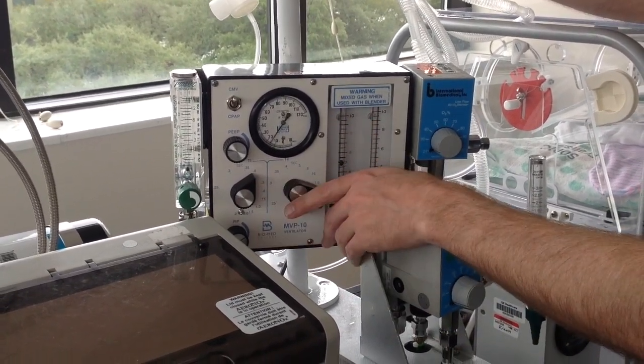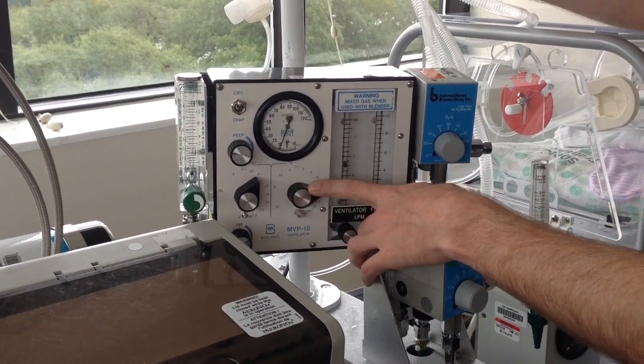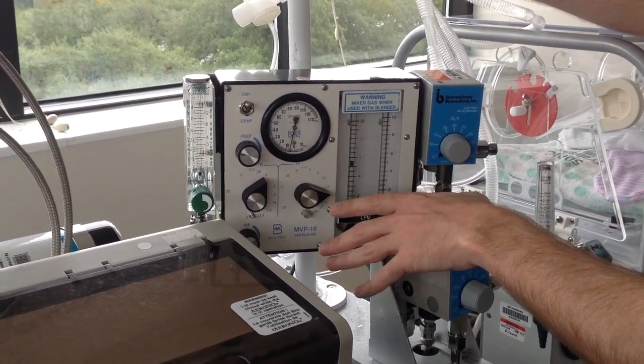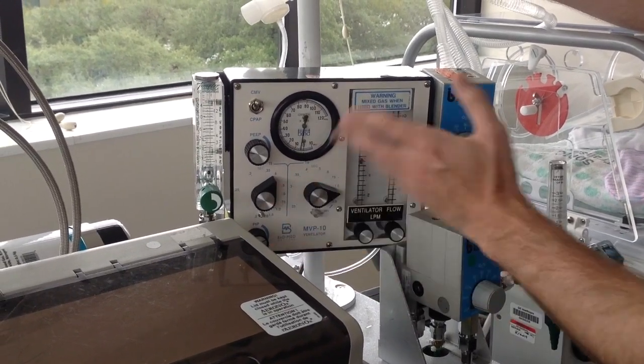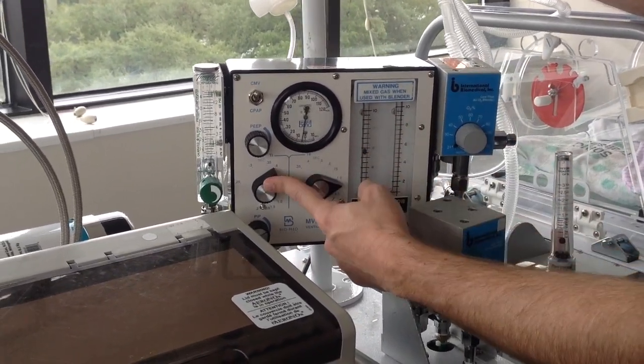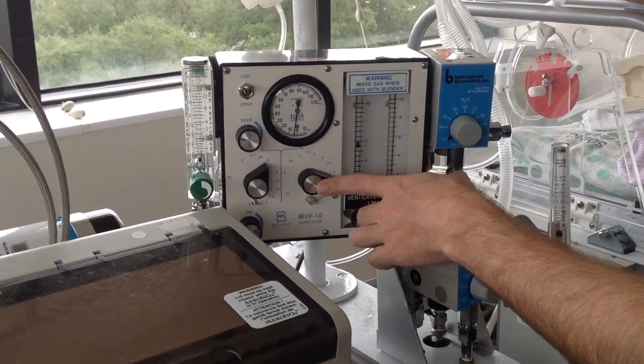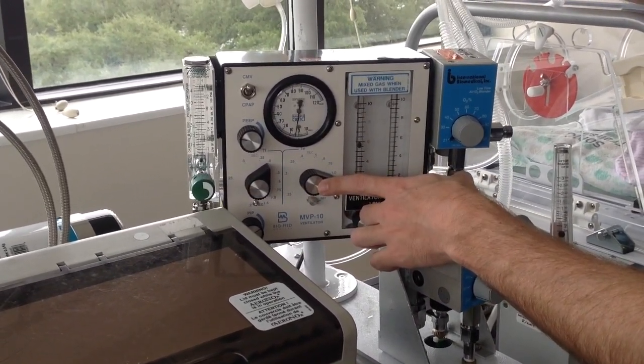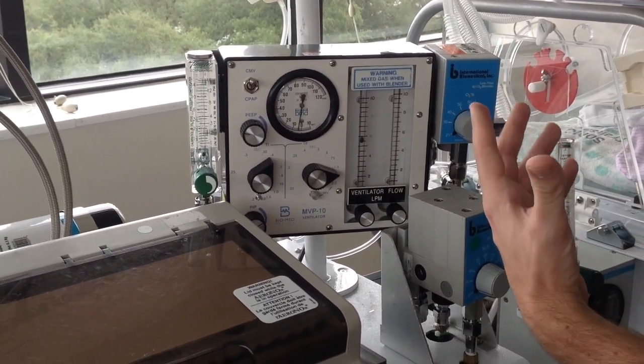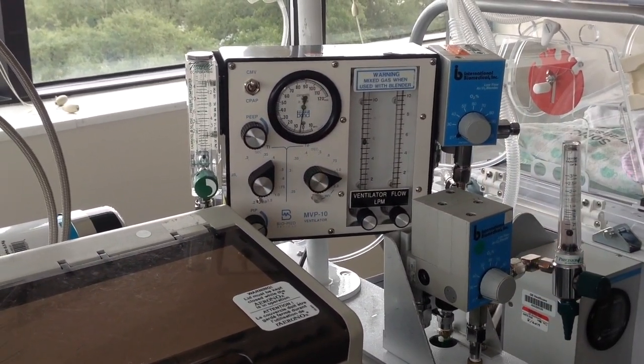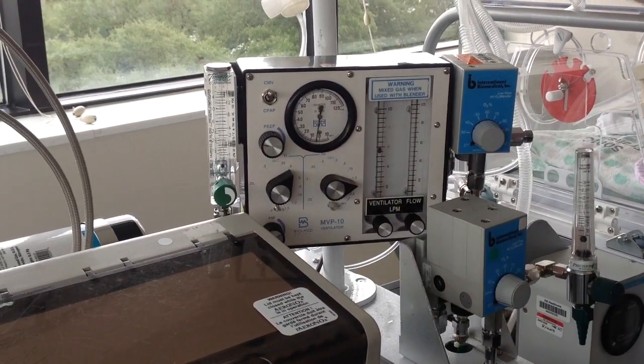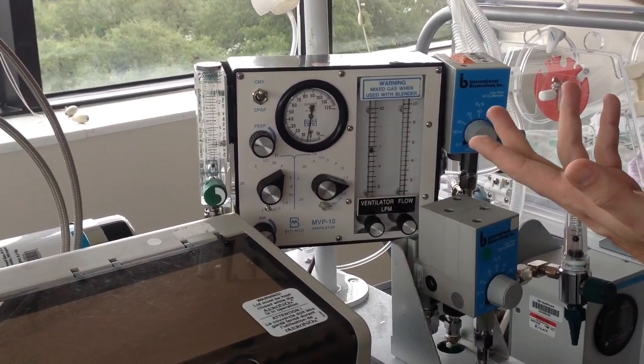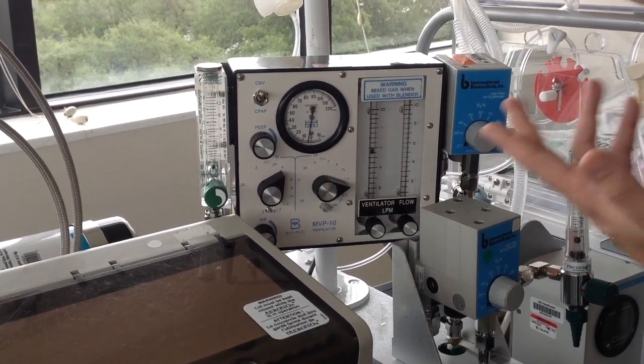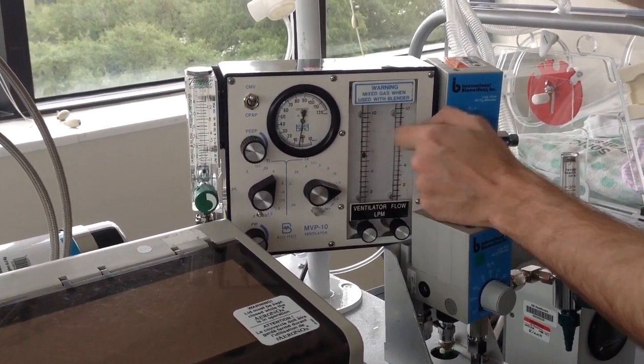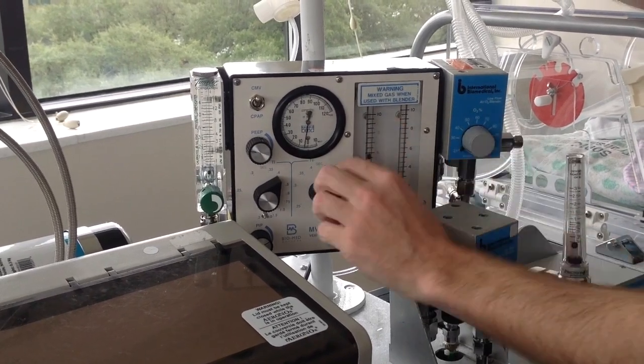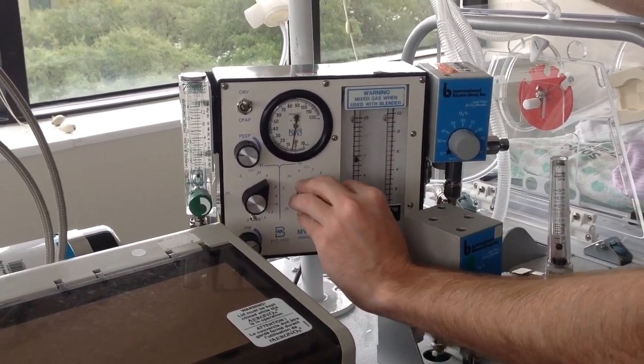to control your rate, you have to set an inspiratory time and an expiratory time. There's no respiratory rate knob, there's no button to tell you what it's going to be. So you need to decide, based on your patient, what you want your inspiratory time to be. Once you've decided that, then you can adjust your expiratory time to get your desired rate. So just as an example, before we do any math, we're just going to listen to it and hear the changes. Let's say we want our I time to be 0.4 seconds. You can hear your rate right now. Well, if you want to have a higher respiratory rate in a minute, you need to spend less time in the expiratory phase. So if we decrease my E time, our respiratory rate is going to go up.